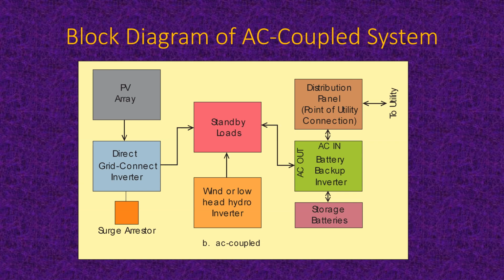So here's what you can do now, and could do for a number of years, is put in a separate standby load panel and connect your direct grid connect inverter to that separate standby panel rather than to your main distribution panel. And then you add the three items on the right, which are basically what we just had in the previous system, a DC coupled system. So you add a battery backup inverter, and the fairly well kept secret there is that that AC out was actually a bidirectional connector. And you can also run AC back into that system.